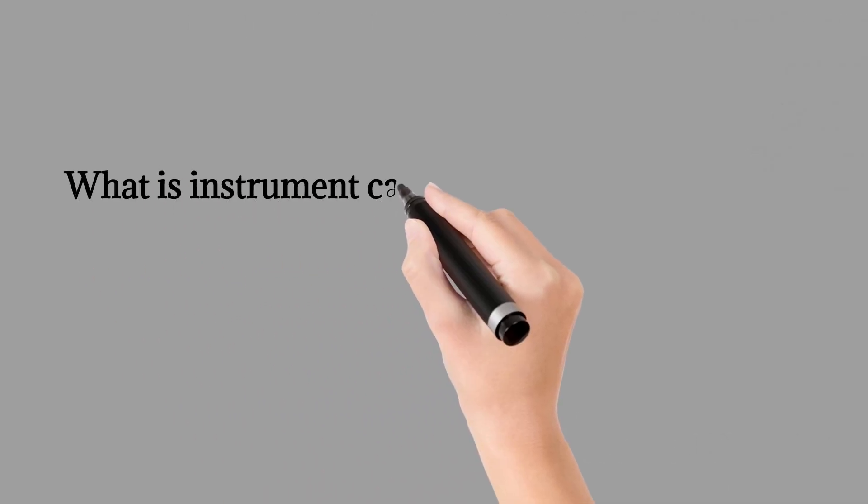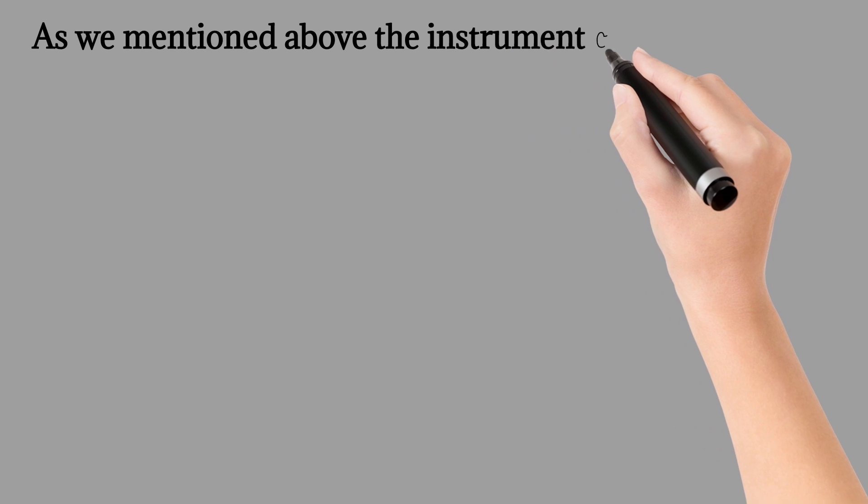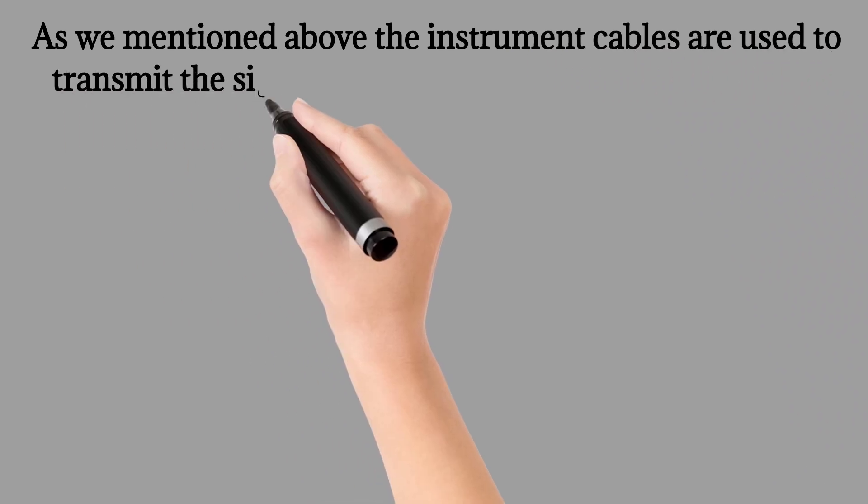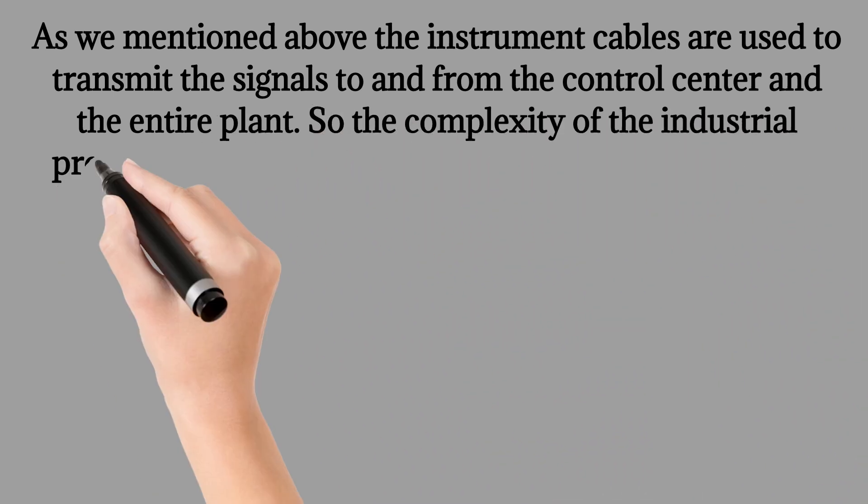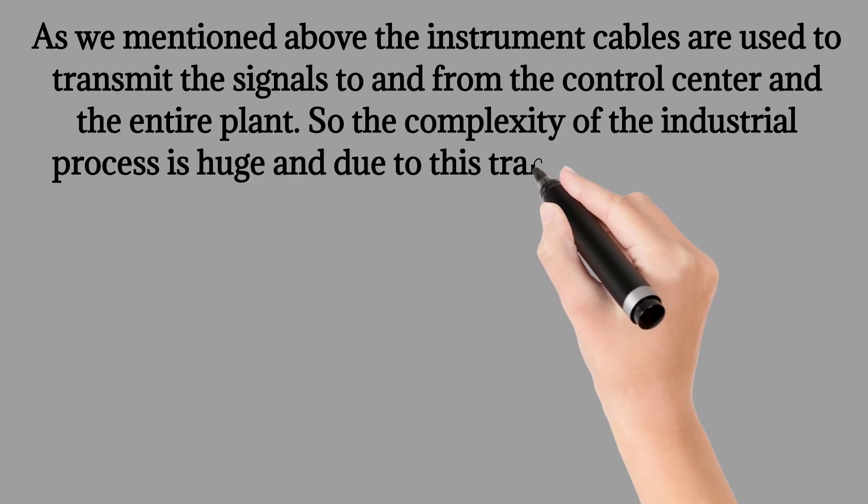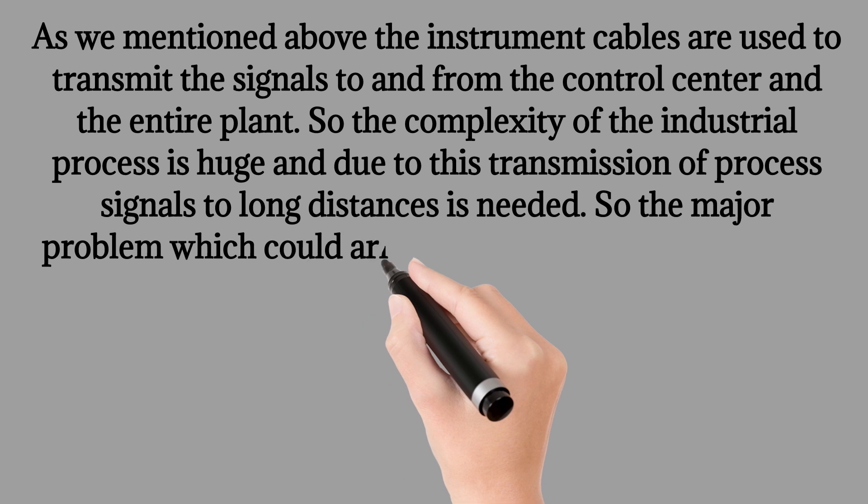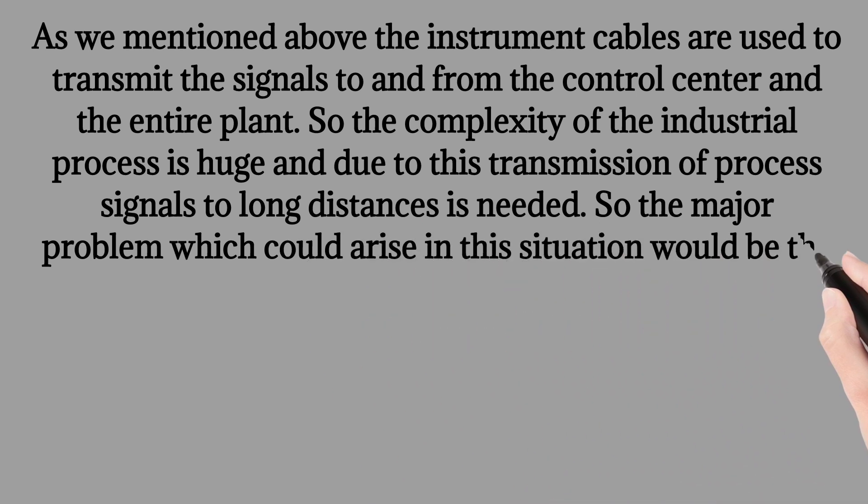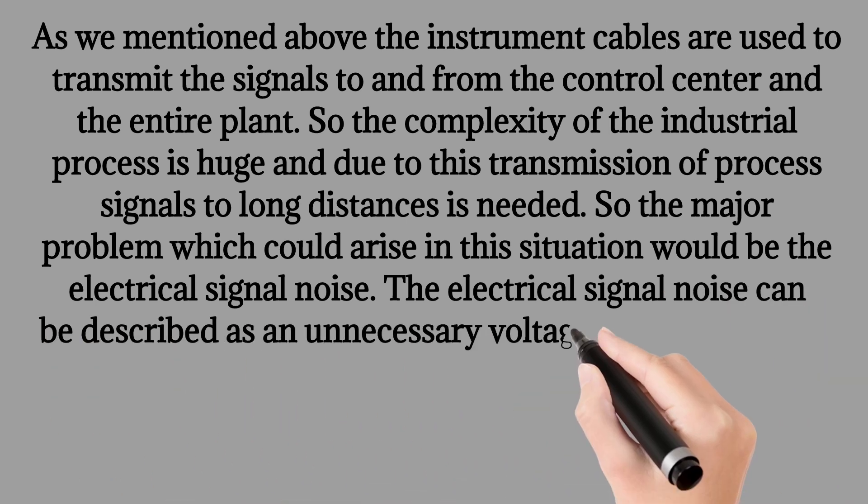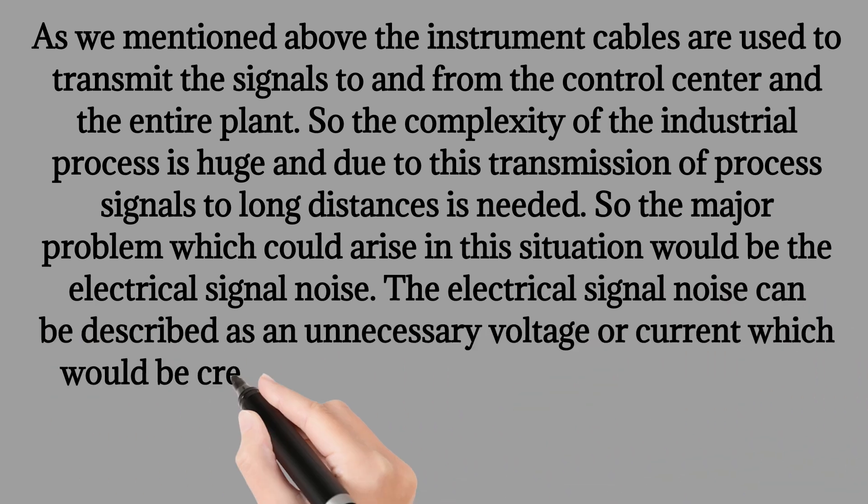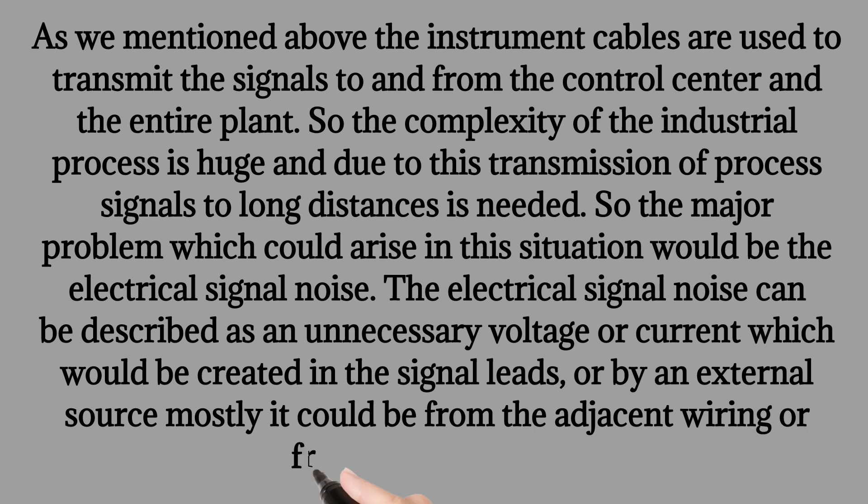What is instrument cable shielding and why is it required? As we mentioned above, the instrument cables are used to transmit the signals to and from the control center and the entire plant. So the complexity of the industrial process is huge and due to this transmission of process signals to long distances is needed. So the major problem which could arise in this situation would be the electrical signal noise. The electrical signal noise can be described as an unnecessary voltage or current which would be created in the signal leads, or by an external source, mostly from the adjacent wiring or from the equipment.